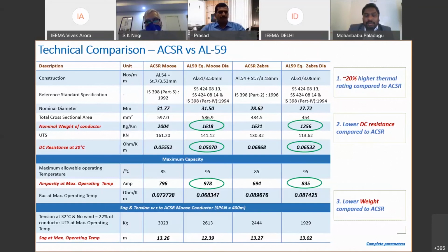The other part is better SAG performance. Better SAG performance compared to ACSR Moose, even at the rated operating temperatures of AL59 Moose. This is also one of the benefits where you can optimize your project cost on the tower design aspects.